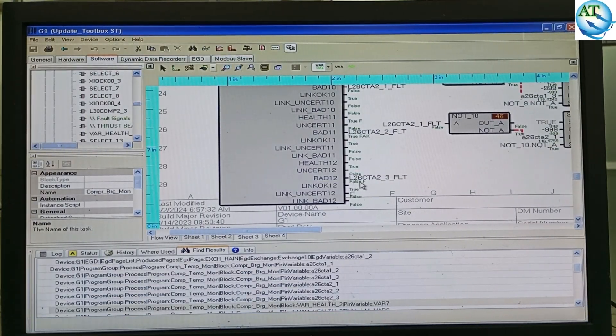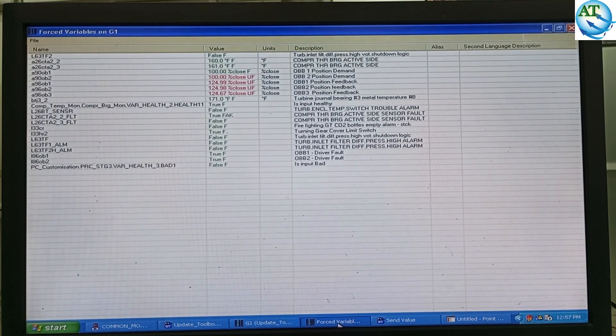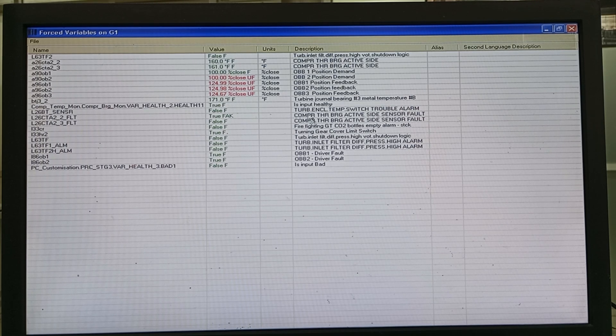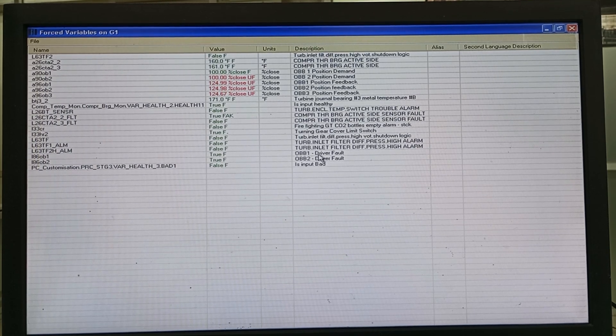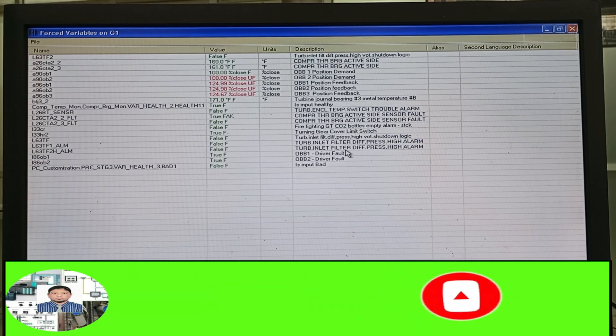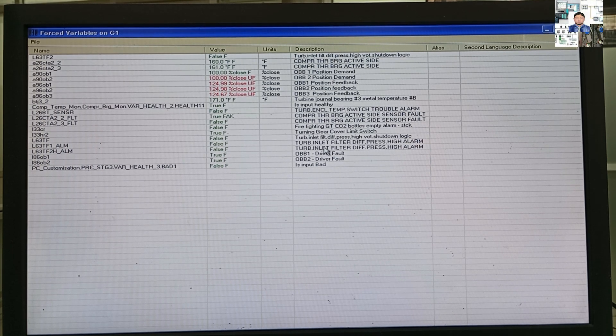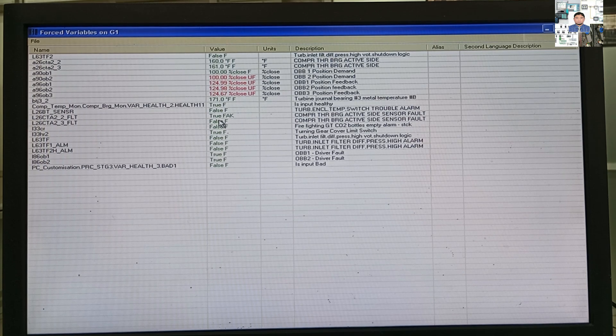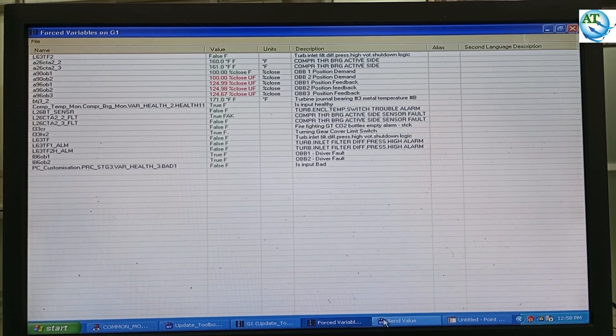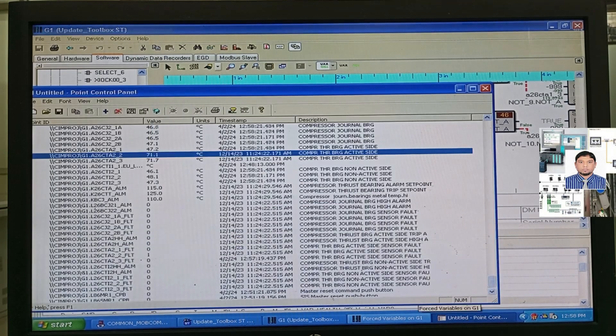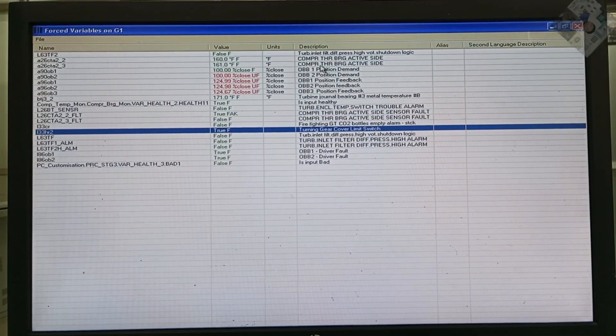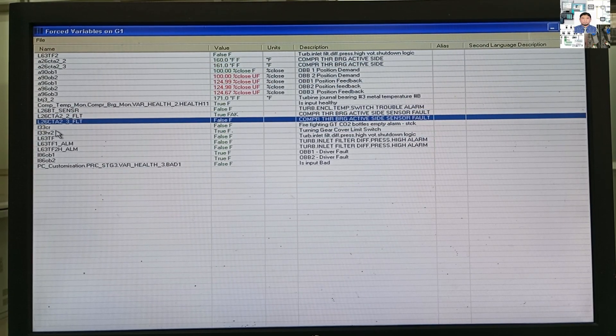Then you can change the element, and afterward go to unforce to make it unforce. I have shown how to force and unforce a digital input or analog input in the GE control system for maintenance or changing purposes. Before changing any faulty field instrument for maintenance, you must first force this value in the system so it does not affect the running condition of the turbine or cause a turbine trip. For any maintenance work or element change, first make the force value, then change the instrument. After completing your work, you can make it unforce. In the list, you can see the force and unforce list in the control system.